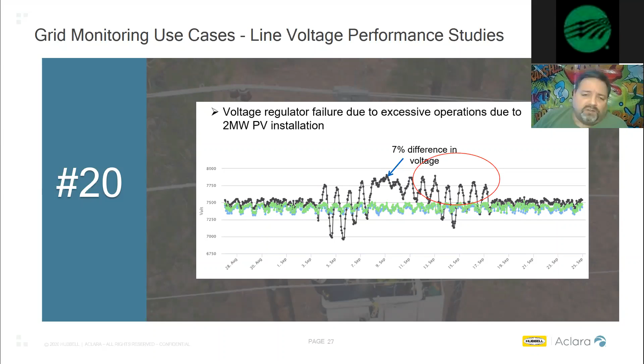We've even had one of our engineers fall in love with our system - Joel Roper, a distribution engineer out of Carroll White in Indiana. He's taken over pretty much almost everything at Carroll White, really into the distribution side of things. He took our sensors, installed them on his lines, and there happened to be a cold spell come through - an Arctic polar sort of event. Joel captured all kinds of measurements during this cold snap and was able to create a line sag study based on temperature.